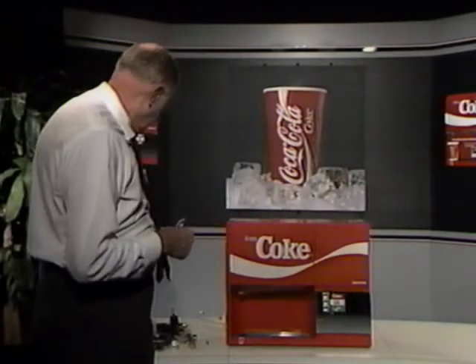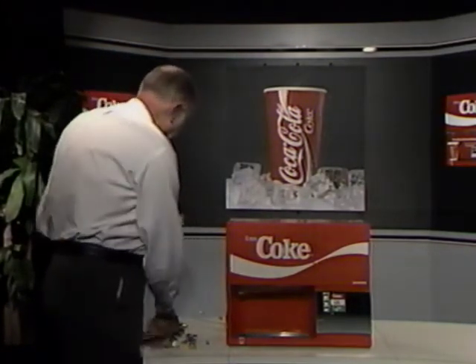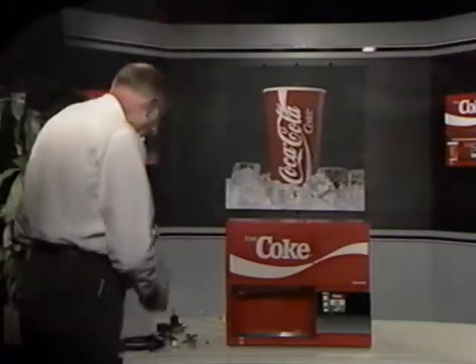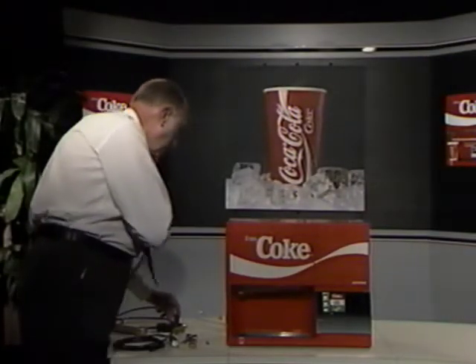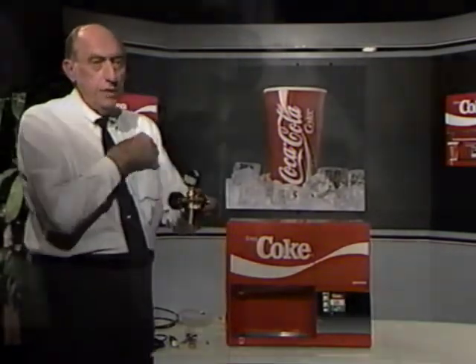Also, for high volume locations, it eliminates the need for multiple cylinders at a location where you may have to have 3, 4, 5, or 6 cylinders, perhaps where there are more than one machines. So the remote CO2 kit was developed for this purpose, and we'll go through the installation procedure. At this point, we'll show you the parts involved in the kit. This is the CO2 bracket, which replaces the CO2 cylinder and its connecting hose. We have a CO2 regulator which connects to the 20-pound cylinder.